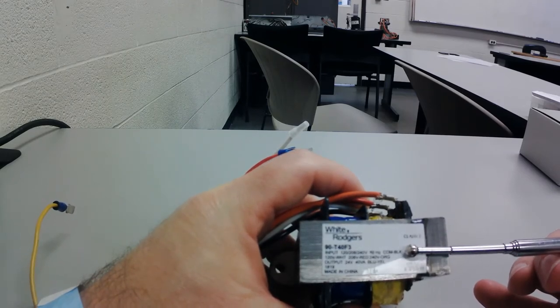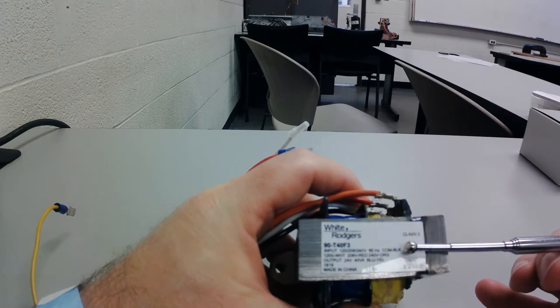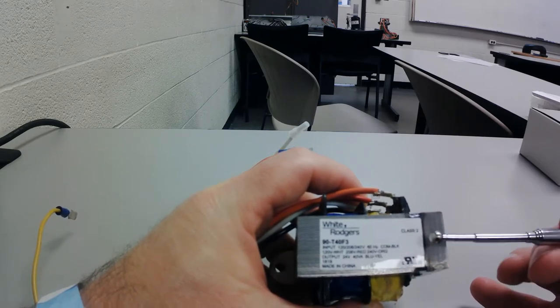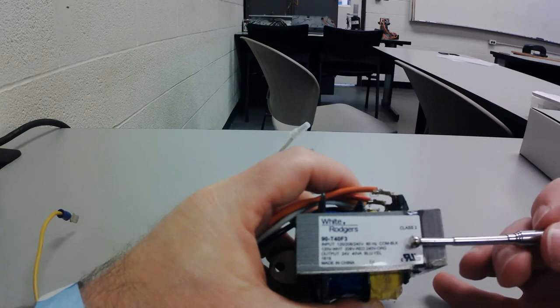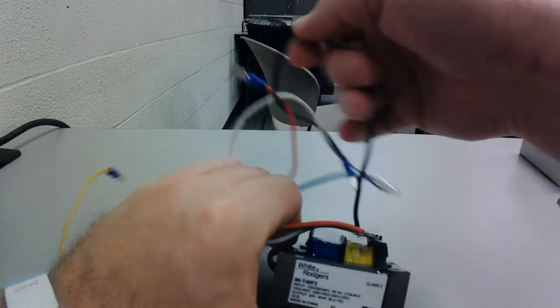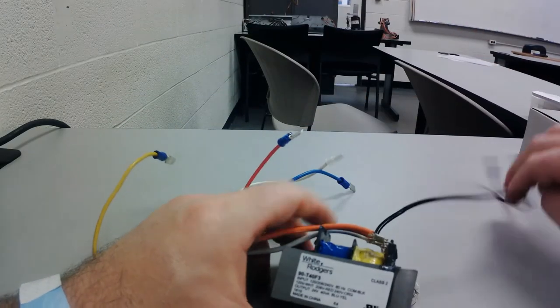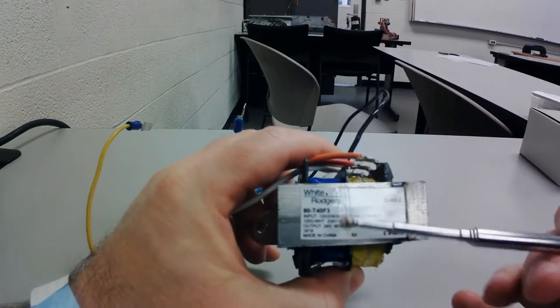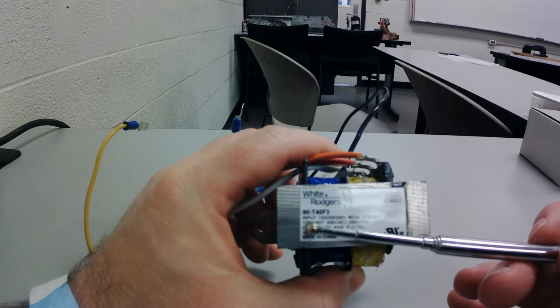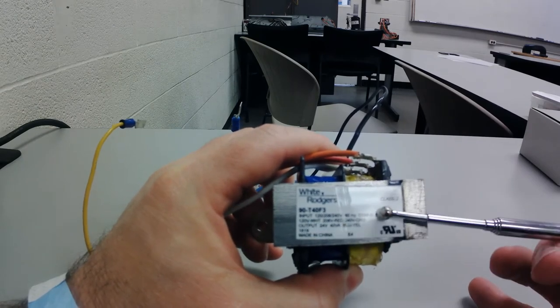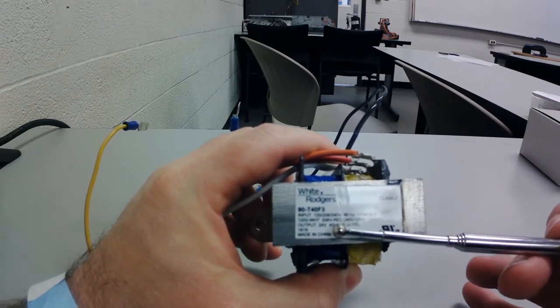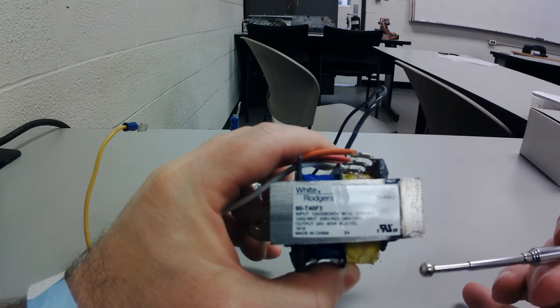If you look right here, at the end of all the input voltage ratings, they're going to tell you that common is black. So no matter what, you're always going to use your return back to power. Common, as they say, is going to be the black wire. No matter what voltage you're going to use, the black is always involved. Okay. So if we're going to use a 120 volt power source, I would use the white wire with the black, and that would leave me the red and the orange unused.